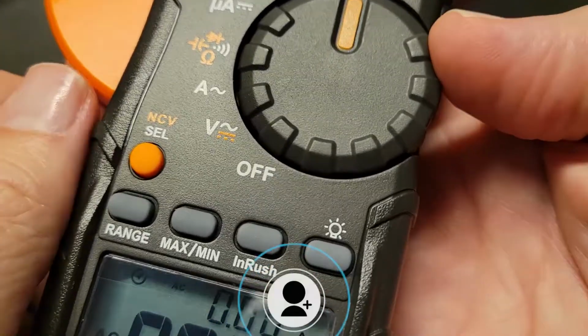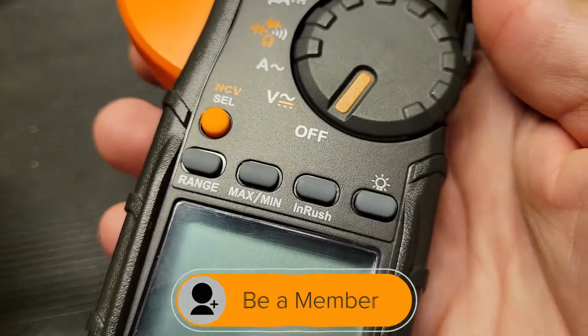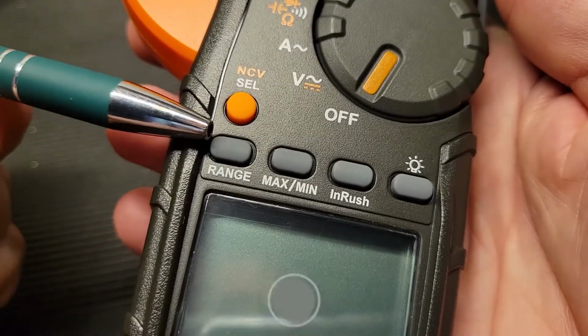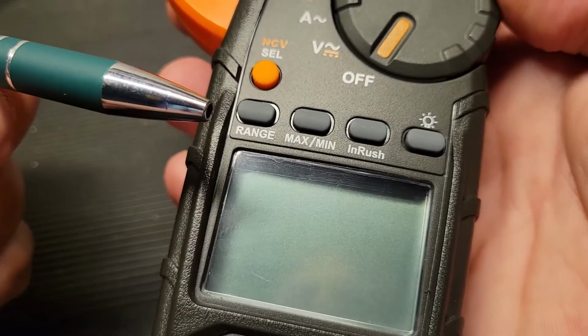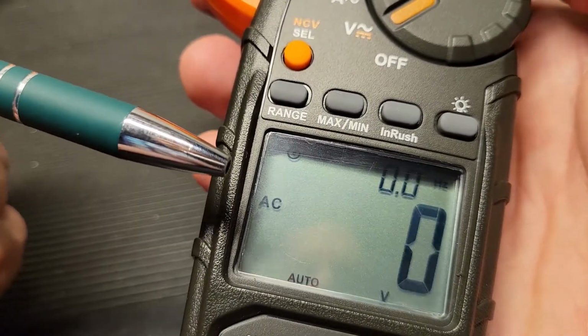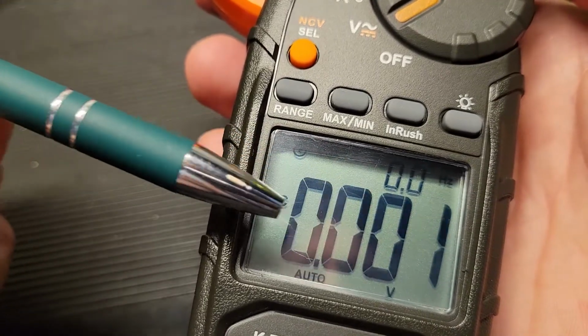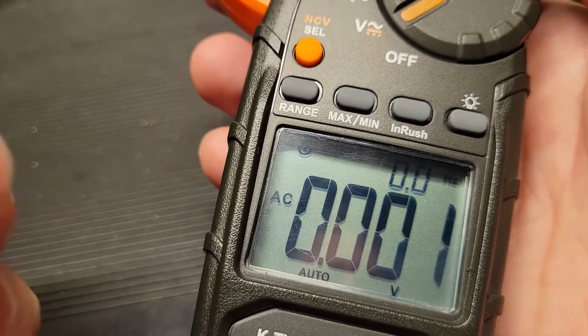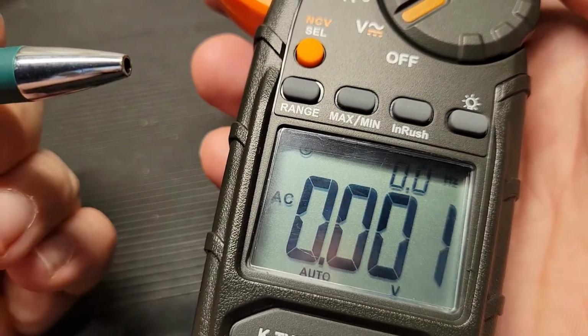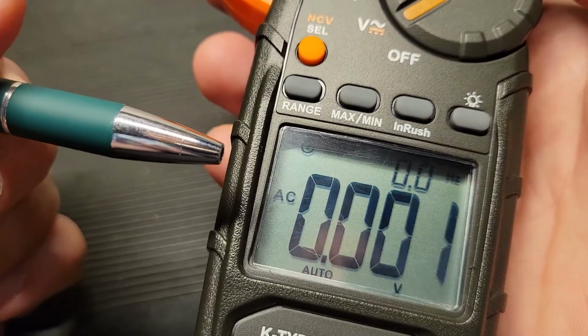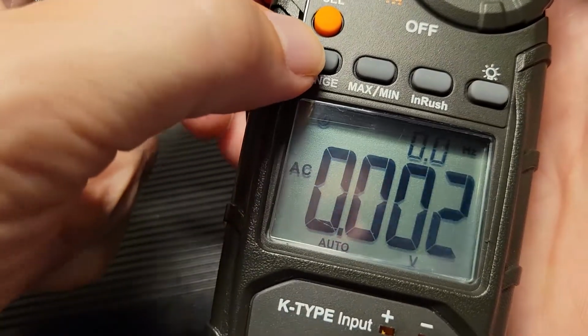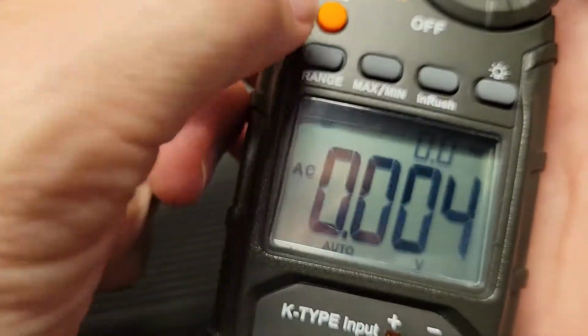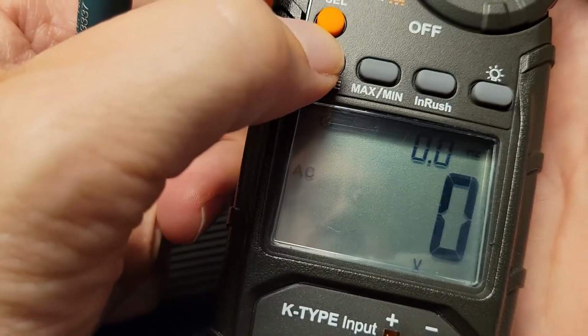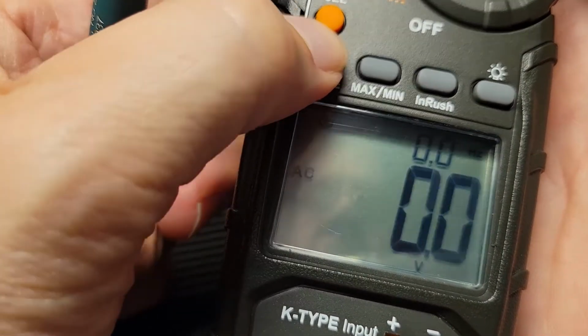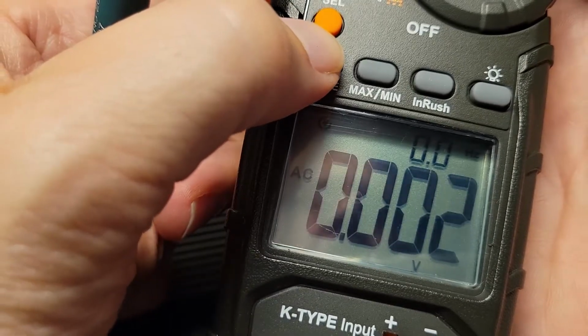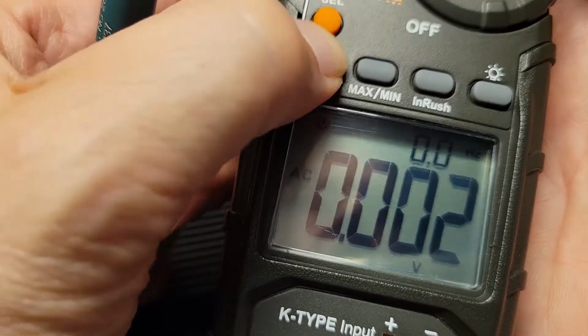So believe it or not, we're almost done with all the controls on this unit. What's left is something that's called range. Now this unit will auto range, which means it will decide on the number of decimal points depending on the amount of voltage or amps or ohms that it's reading. But should you decide you want to control the range, you certainly can by simply pressing the button, watch the decimal point. It will allow you to control the amount of resolution you get for that reading.